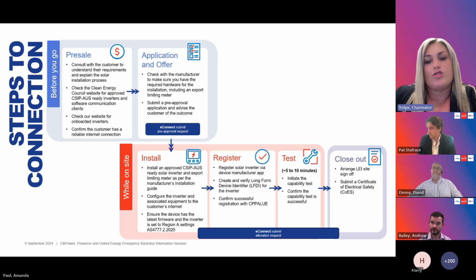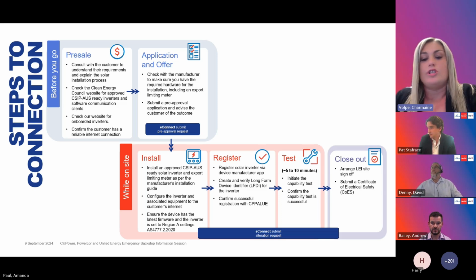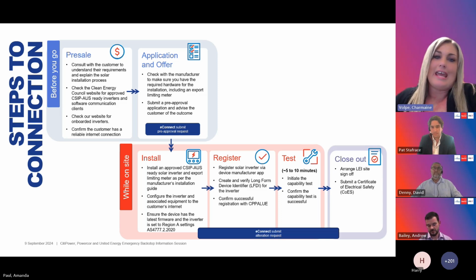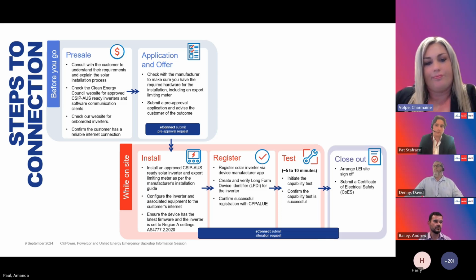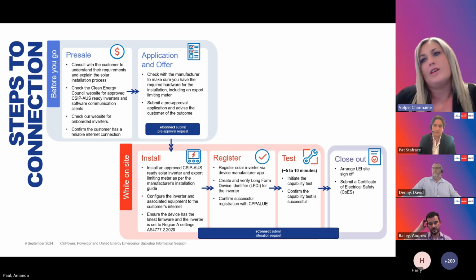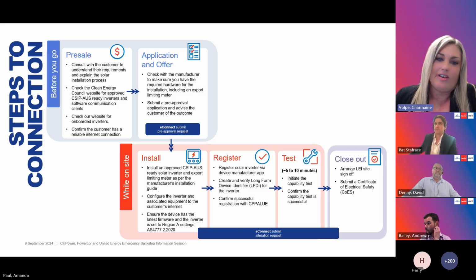For installations greater than 30 kVA and equal to or less than 200 kVA, the solar installation must be emergency backstop enabled. So if not via internet connection, they have to install a generator monitor meter as an alternative solution. However, the easiest and most cost-effective solution is a reliable internet connection. It's going to be really important that customers are across all of this so they can make a well-informed decision on their investment and understand their requirements.